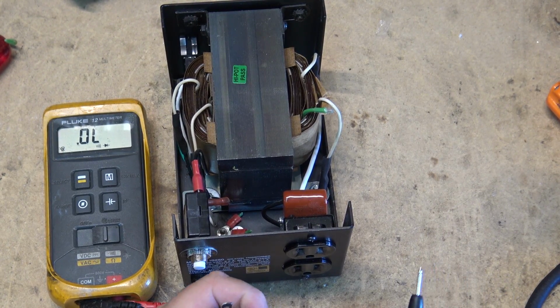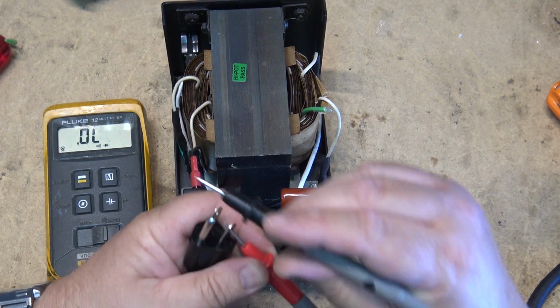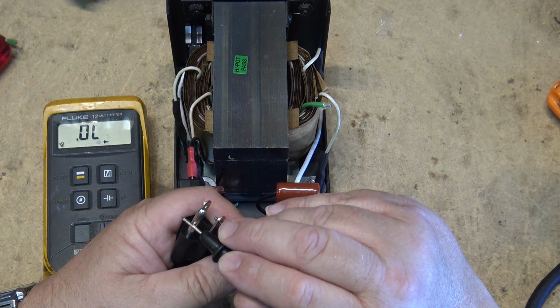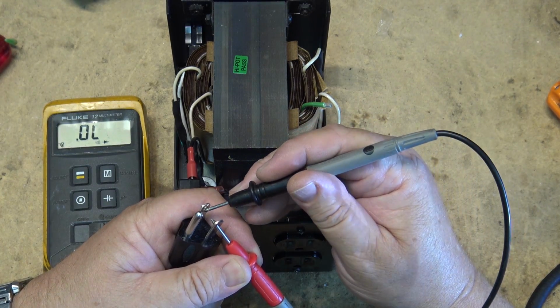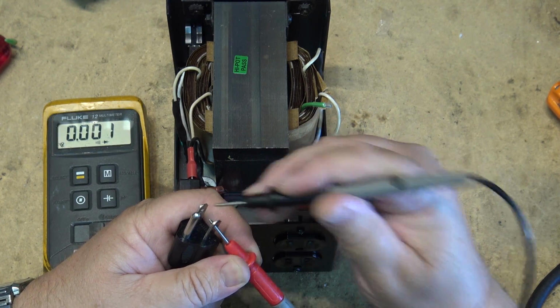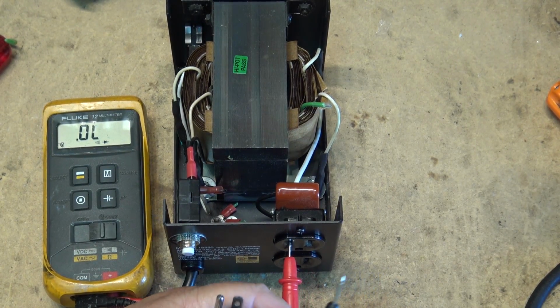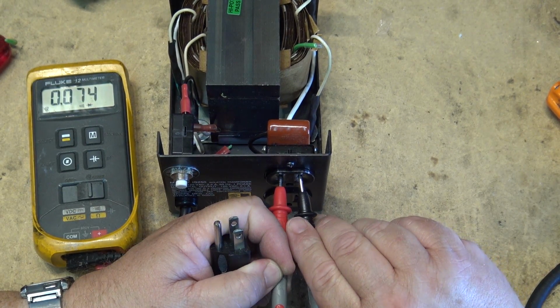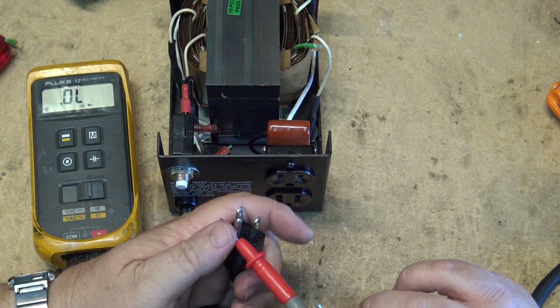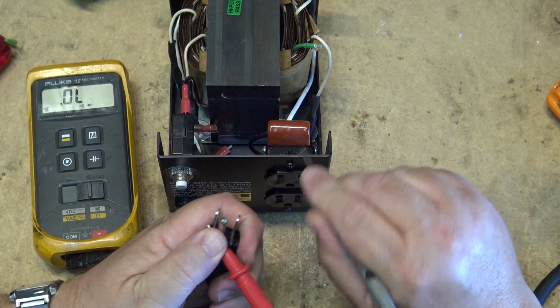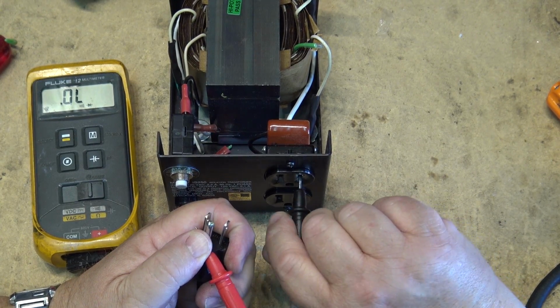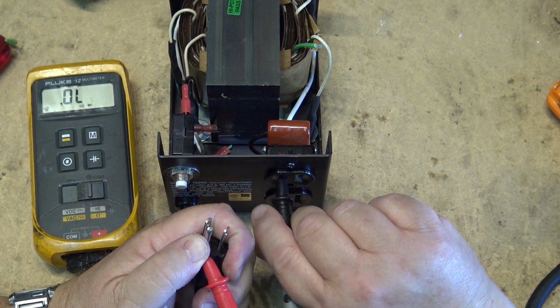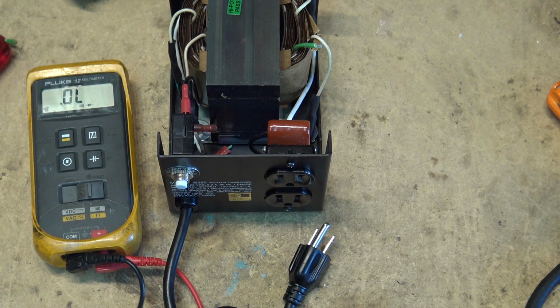If I check continuity between the pins here, you'll see that there is no continuity between the power plug. There will be through the primary, which is normal, and there will be on the secondary here, which is normal, right? But no continuity between the ground and any of the outlets. This unit is 100% totally isolated.